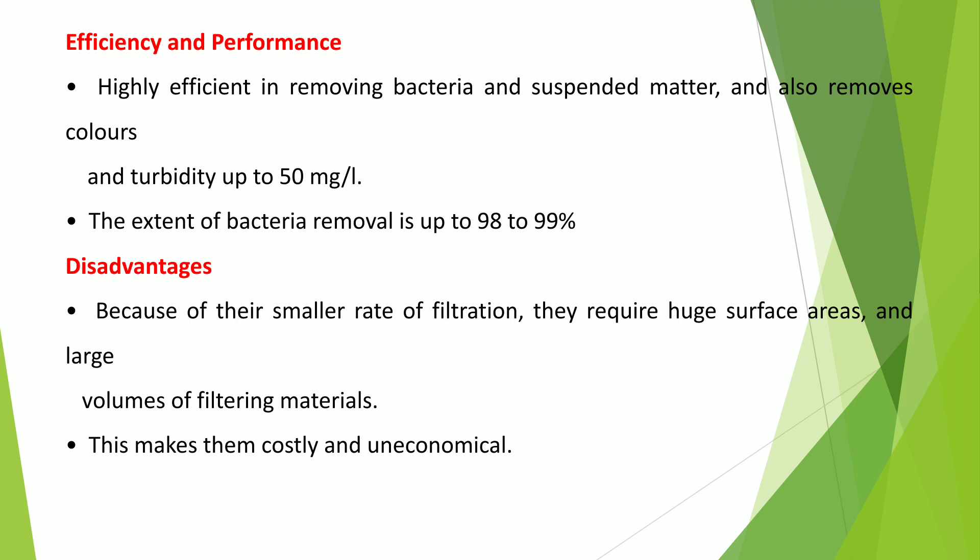Slow sand filters are highly efficient in removing bacteria and suspended matter, removing colors and turbidity up to 50 mg/L, with bacteria removal up to 98 to 99%. The main disadvantage is the very small rate of filtration, which is the actual meaning of 'slow' sand filter. Because of this slow filtration rate, they require huge surface areas and large volumes of filtering materials, making them costly and uneconomical.